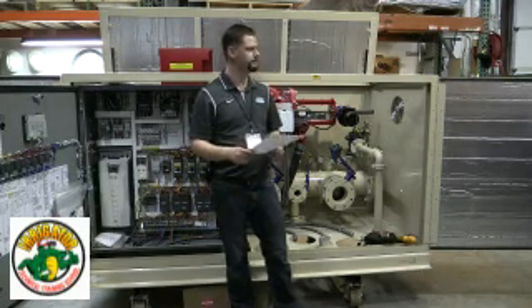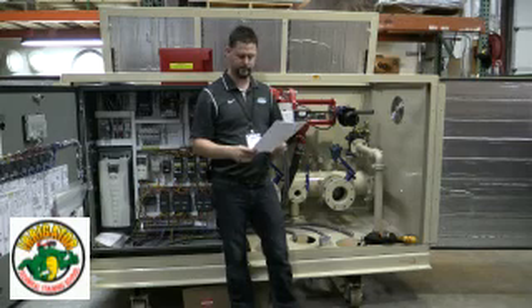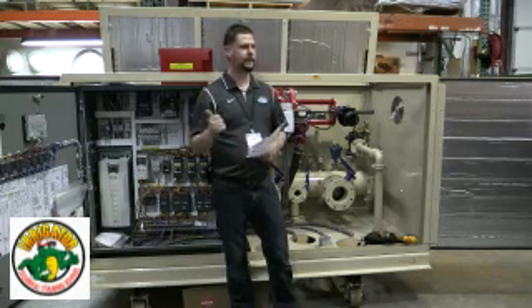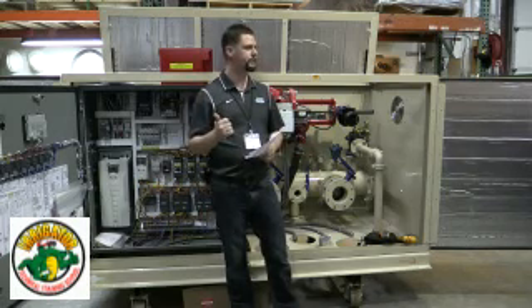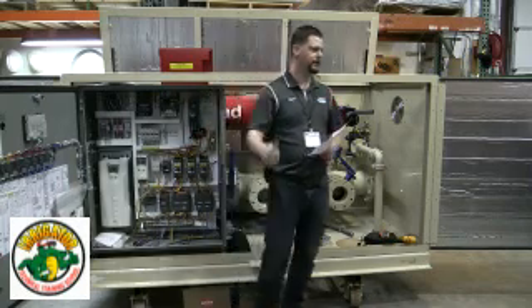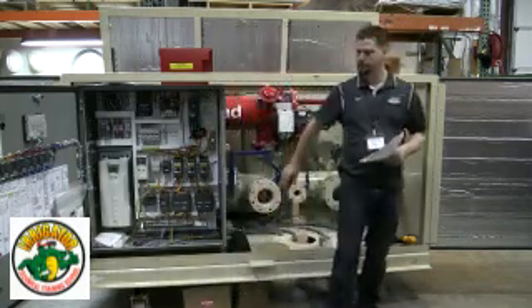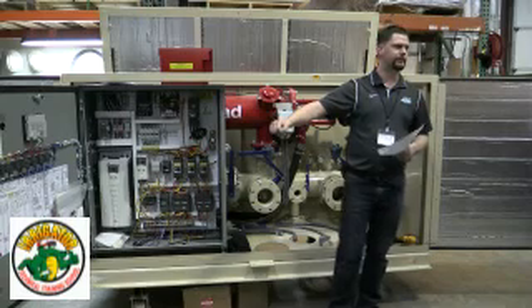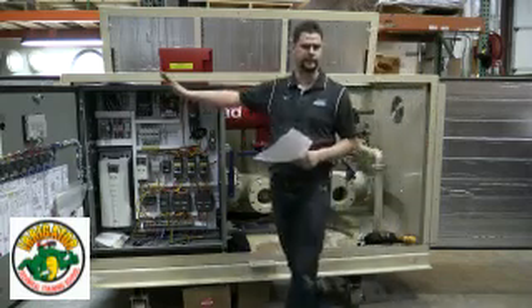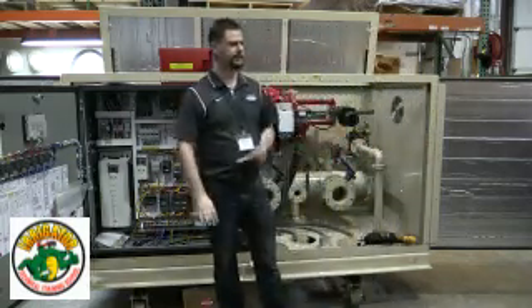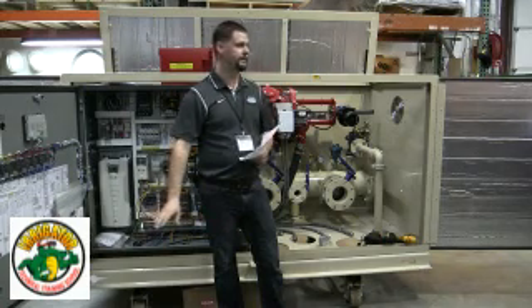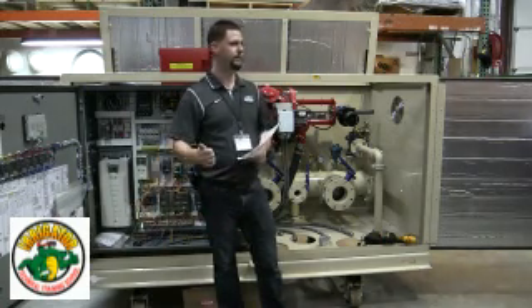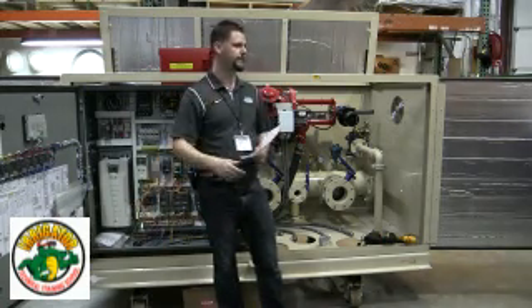Check that. Yeah, ball valves, man. So if I have that opportunity, I always try to have them blow out their main line first. The first thing I do is shut the isolation valve to the pump station, isolating it from the system, and that's the only valve I'll leave shut throughout this whole process, even after I leave.